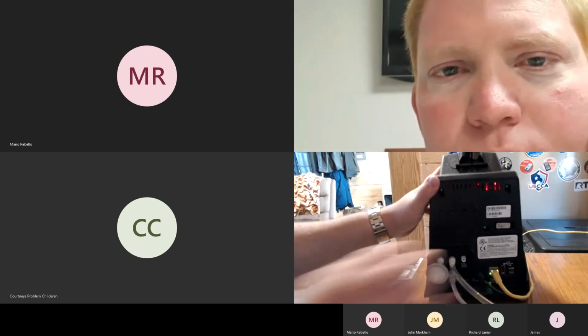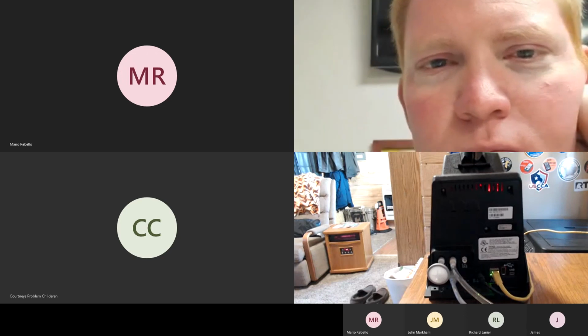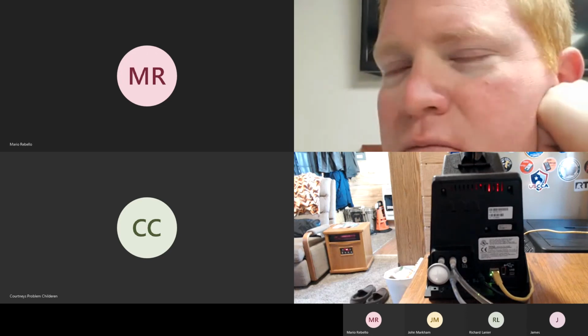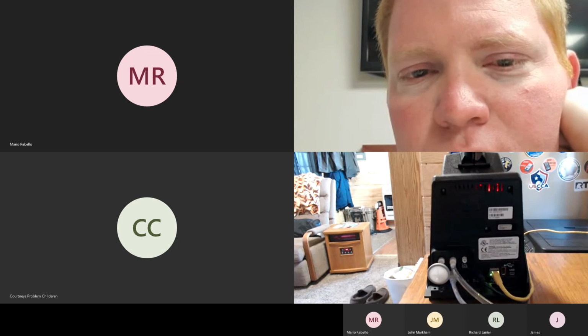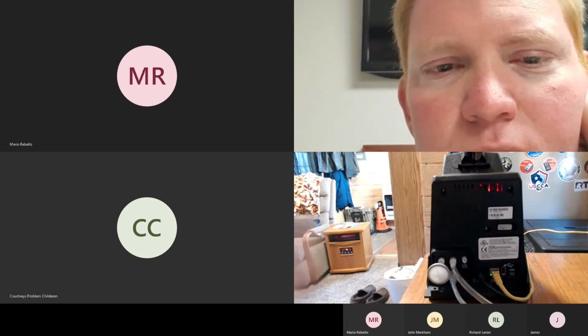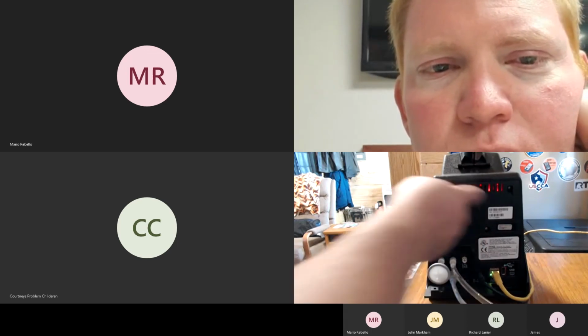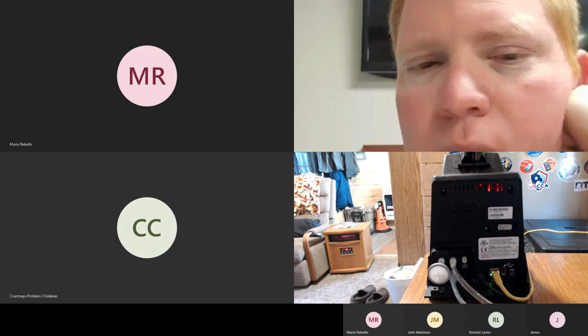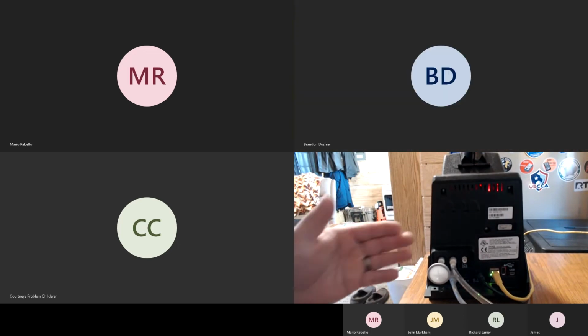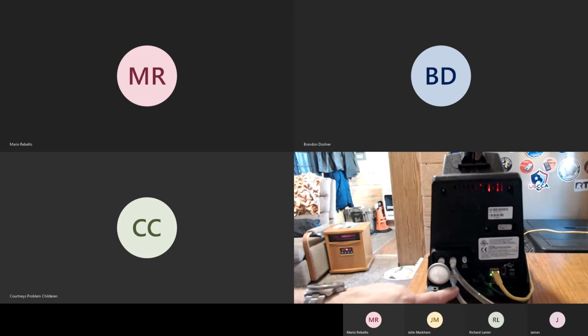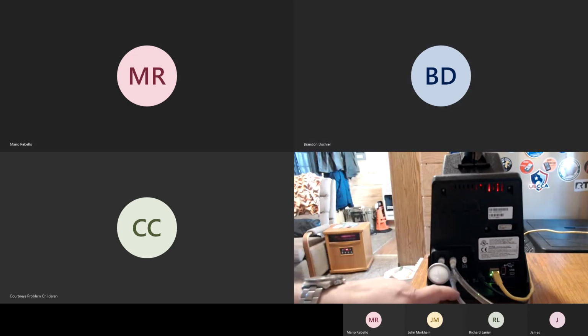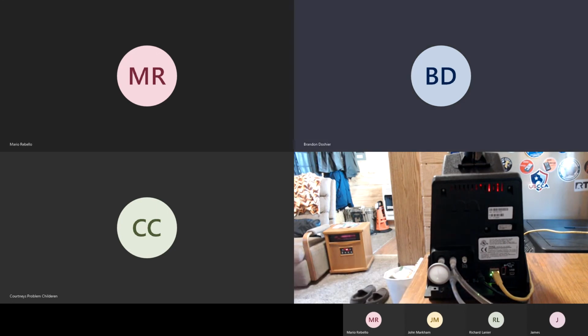If you have separate bottles of gas, say you have HCN or SO2 or something that is not in your mix bottle, you would have that hooked up to port 3, or if you have the 6-port model, you would have it connected up here through ports number 4 through 6. And again, make sure that the tubing and the card reader cable for each bottle is on the same exact port, because if they are on different ports, it will suck air from the wrong tubing connection trying to get gas.